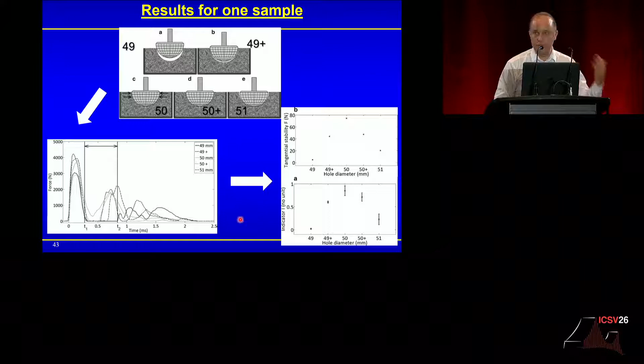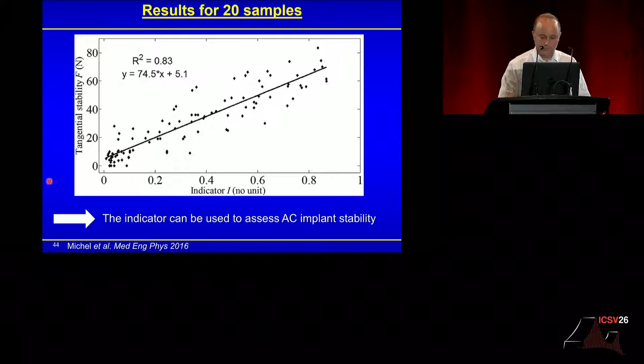But that's, of course, for one sample. We need to do a lot of samples using the same time window, the same way of measuring the indicator. And that's what you get for 20 samples. When you put all results together, you see here the tangential stability, and here the indicator, and you see that you get a pretty good correlation between the stability on one side and the indicator on the other side. So it means that there is information on the implant stability that you can retrieve in a non-destructive manner using a simple impact hammer.